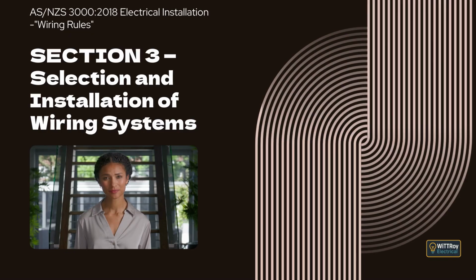Clause 3.10.2 Wiring enclosures. This clause introduces the requirements for wiring enclosures used to protect cables that require enclosure. Clause 3.10.2.1 Types. This clause explains the acceptable types of wiring enclosures. These include conduits complying with AS/NZS 2053 or AS/NZS 61386, such as steel conduit, flexible metal conduit, rigid or flexible insulating conduit, and corrugated insulating conduit. It also includes cable trunking systems complying with AS/NZS 4296, with or without compound filling, and other enclosures that provide mechanical protection at least equivalent to conduit or trunking.